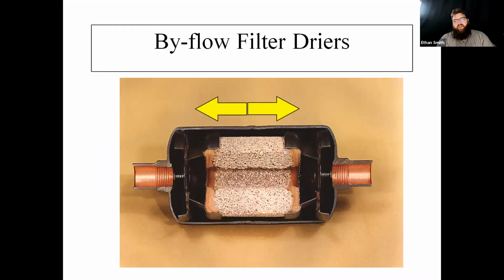Biflow filter dryers are kind of unique here, guys. This is a cutaway of one that I got a hold of. And you notice that there are check valves on either side of this filter dryer. The reason for that is filter dryers filter from the outside in. If this were just a single flow filter dryer, we would always have refrigerant moving through in one direction. But because we're going to have refrigerant move through in two directions, we have to make sure somehow that these things always filter from the outside and push out the inside. Otherwise, when we reversed cycle, we would simply take all the junk on the outside that we had filtered out and push it back into the system when we change directions.